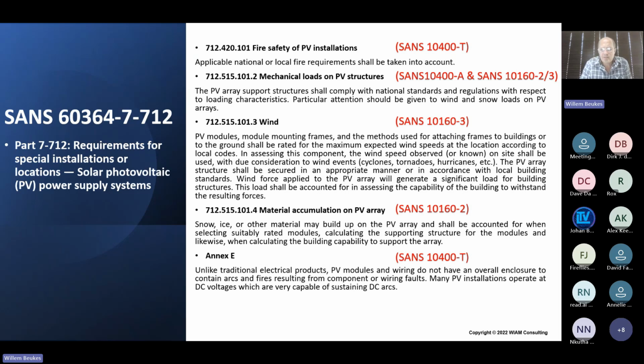And then in Annex E of SANS 60364, it says that the electrical products on a PV system do not have an overall enclosure to contain the arcs or fires resulting from the components or wiring faults. Many PV installations operate DC voltage, which are very capable of sustaining DC arcs, which refers to SANS 10400T in terms of the compliance for electrical installations.